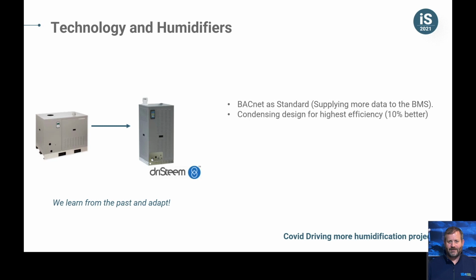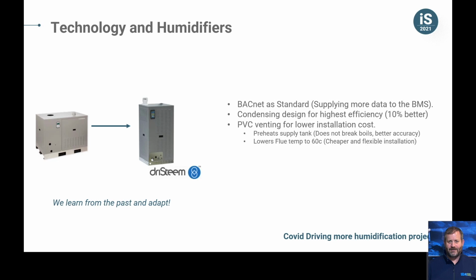With the new condensing design, they're 10% more efficient than their predecessors. PVC venting for lower installation costs. Again, mechanical cost is key. So these units can be installed directly on the rooftop with an outdoor enclosure, or they can be vented through the side wall of a building with PVC. You no longer have to have stainless steel venting because of the high flue temperatures. Having a lower flue temperature is also part of the technology of the unit.